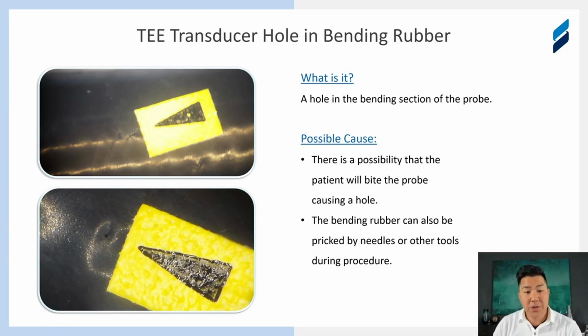Now these pictures are taken under high magnification. These are very small, and we really recommend that the sterilization department have a nice magnifying glass with good light to be able to inspect the bending rubber and the tip too for any damage. As you can see, these are very small holes, like pin needle. These are likely caused by very sharp instruments during the procedure and are often not really visible on a casual glance of the transducer. So a magnifying glass is really important with some good light.